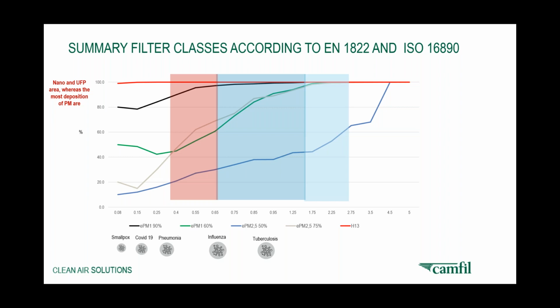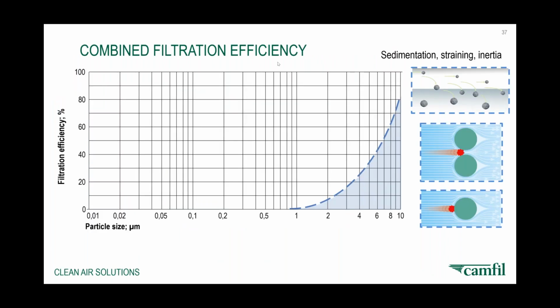So if we look at how a HEPA works, all filters capture particles. Often the first idea of a filter is that it's like a small net or it's a small pore, so particles don't fit through that net. And that is true. Sedimentation and straining and inertia and various properties happen that if a particle is too big to get through the actual structure of the filter, like a fishing net, it'll block particles. But that's only one part of the picture, and it's not so relevant for HEPAs because HEPAs operate at much smaller particles, which would find their way through most of those regular HVAC filters we've discussed.